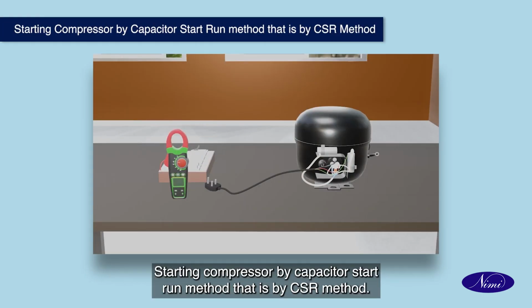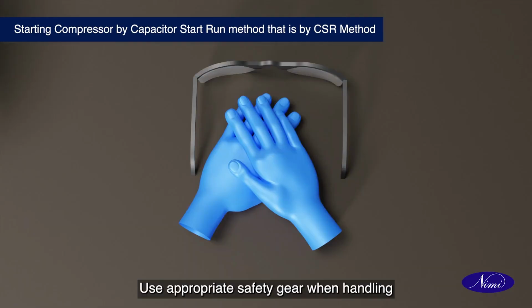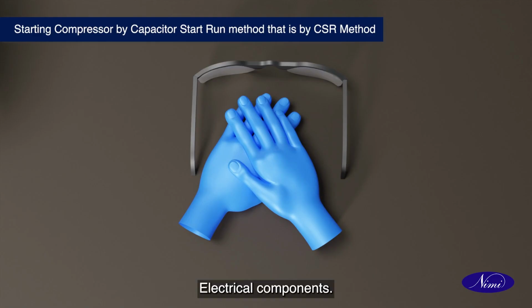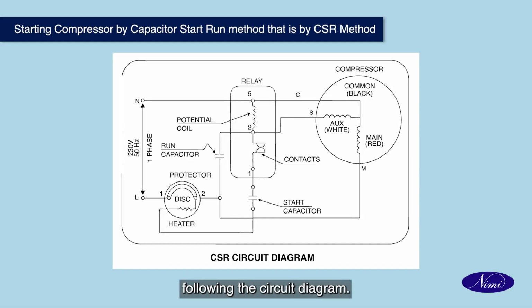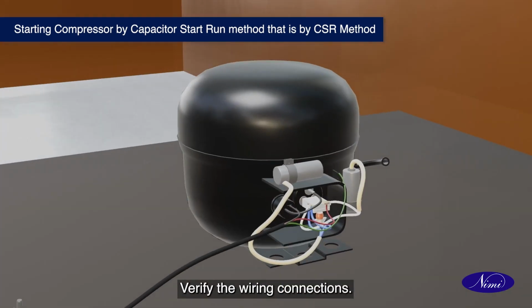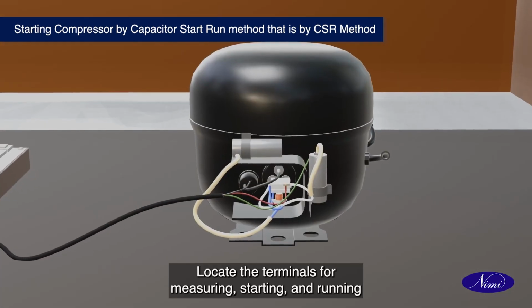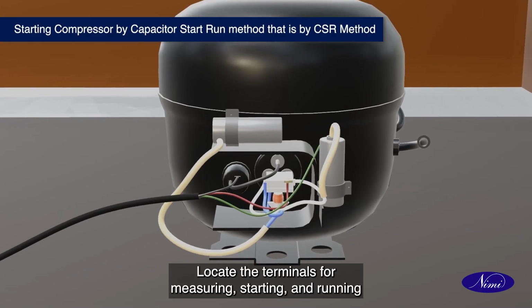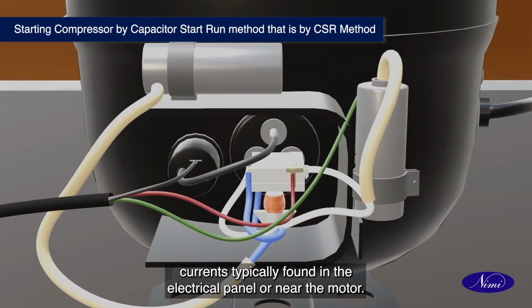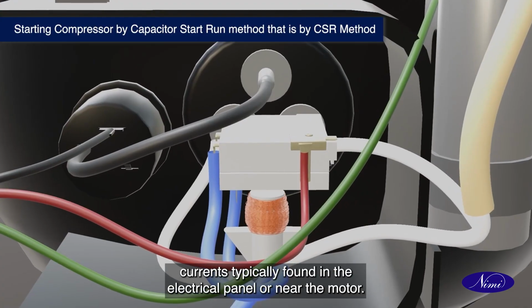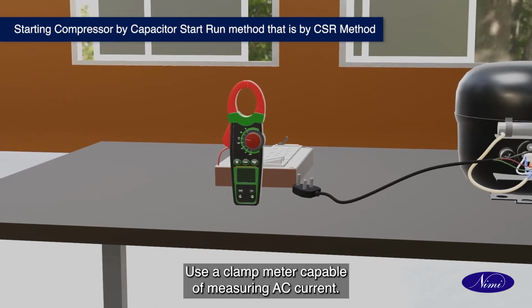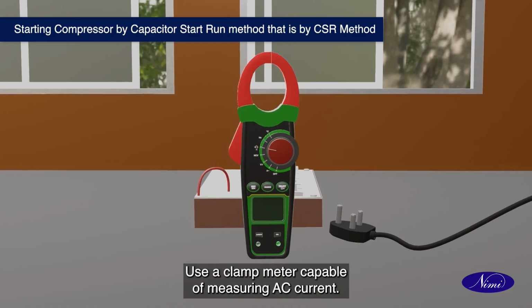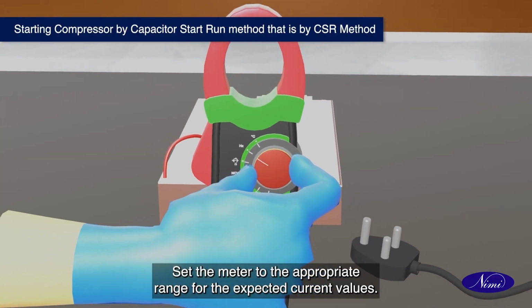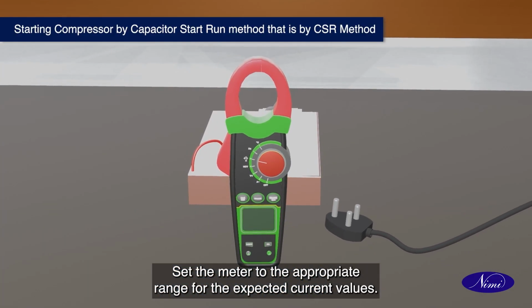Starting compressor by capacitor start run method, that is by CSR method. Use appropriate safety gear when handling electrical components. Connect the components following the circuit diagram. Verify the wiring connections. Locate the terminals for measuring starting and running currents, typically found in the electrical panel or near the motor. Use a clamp meter capable of measuring AC current. Set the meter to the appropriate range for the expected current values.